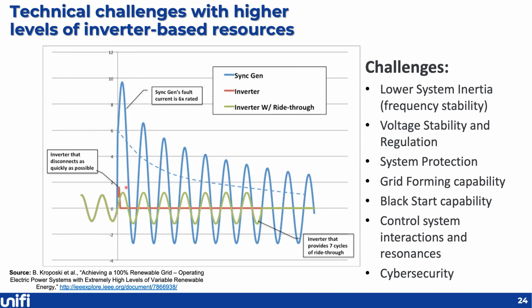That can best be understood by looking at this graph here. System protection is basically how we design the grid and protect it from fault conditions. If you take a look at different fault characteristics, these are output curves from a fault when it happens at this time. For a synchronous generator, when a fault condition occurs, you would get a really large spike in output current, and then it declines over time. This is a pretty big spike, and this is how we often use overcurrent protection. We can recognize this really large bump in output current provided by synchronous generators.